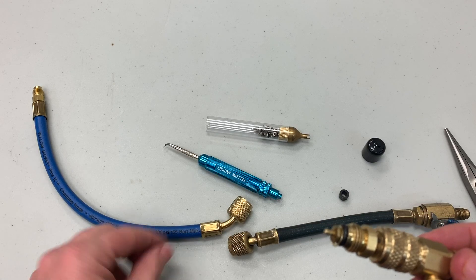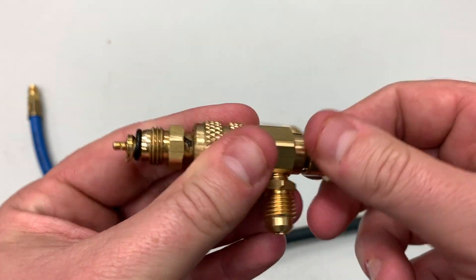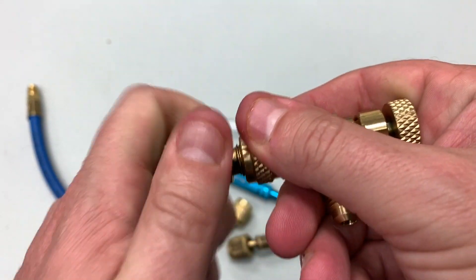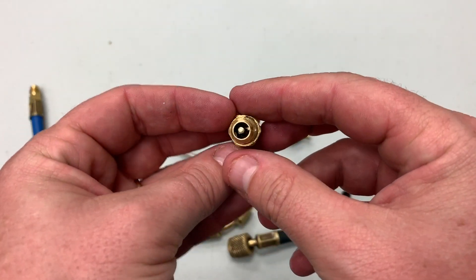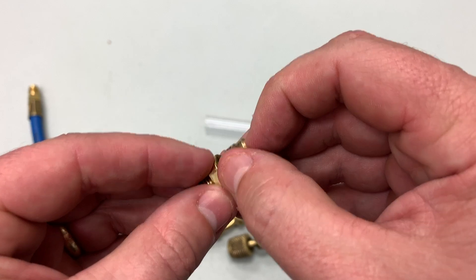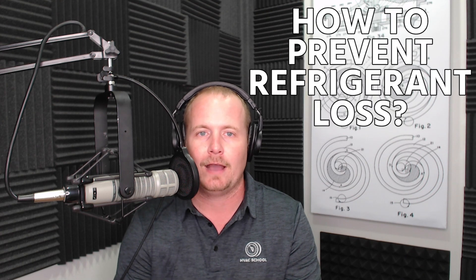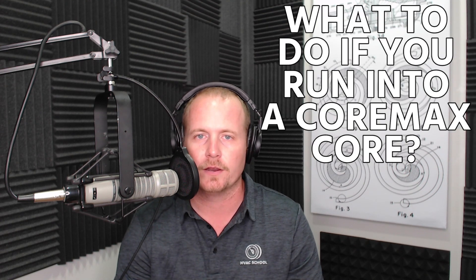Hopefully that's instructive — how to replace the seals, how to set your core depressors as far in as possible while still depressing the cores for refrigerant flow, and what to do if you run across a CoreMax core. The biggest mistake I see technicians make is trying to use a hose that does not have a core depressor on a Schrader core — you won't get any flow at all. Thanks for watching — hopefully that helps with seal replacement, preventing refrigerant loss, and handling CoreMax cores on commercial units.